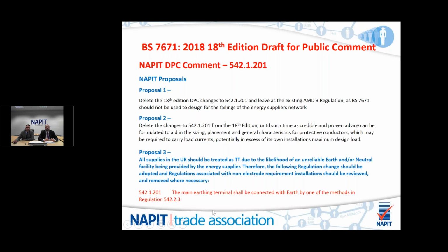So we've got two or three proposals that we will be putting forward, varying slightly. First one, delete the 18th edition DPC change and leave as the existing regulation. BS 7671 should not be used to design for the failings of an energy supplier's network. Delete the changes to 542.1.201 until such time as credible and proven advice can be formulated. So take it out, and if you must put it in, do so at a time when you can give the correct information to those designing installations to take account of this.